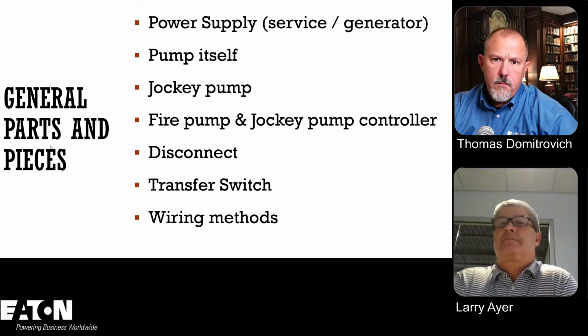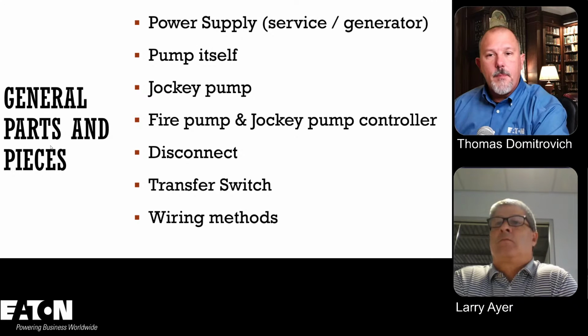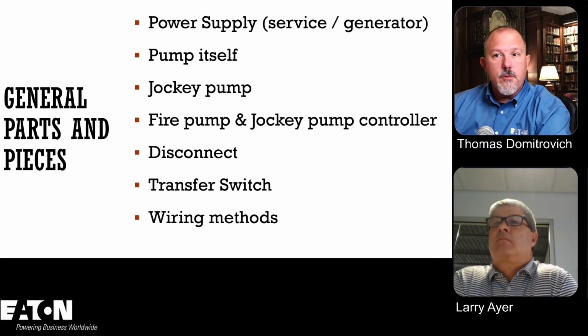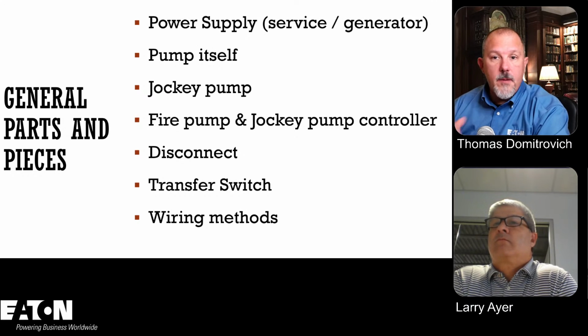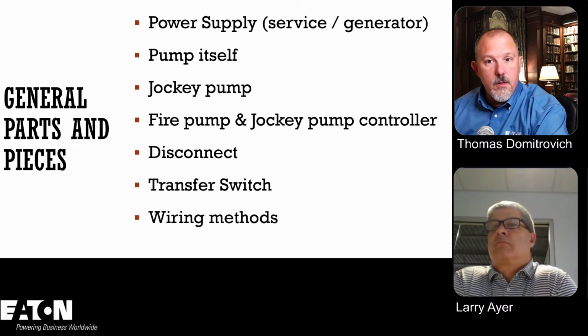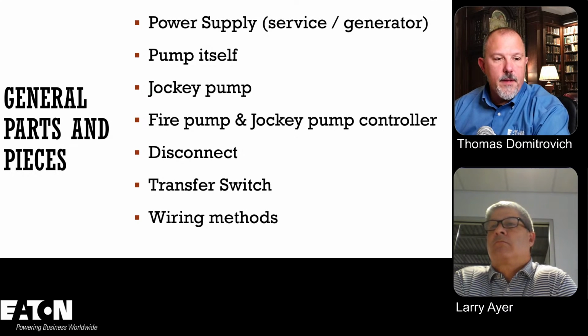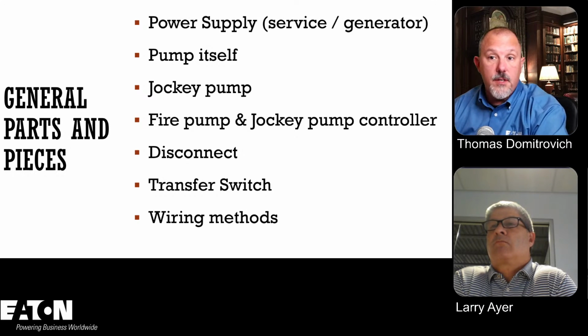Gotcha. So obviously you have the power supply, which could be a service or a generator, and we're going to get into those details. You have the pump itself, the jockey pump, and we're going to talk about that. And then you have the controllers, a fire pump controller and a jockey pump controller. I'm not sure, but those are probably separate components, at least that's the way I've seen it. You have the disconnect, obviously, and some of that can be combined into the pump controllers.